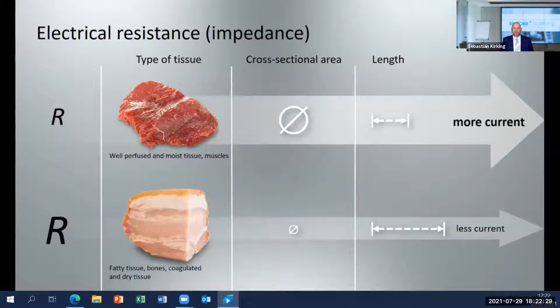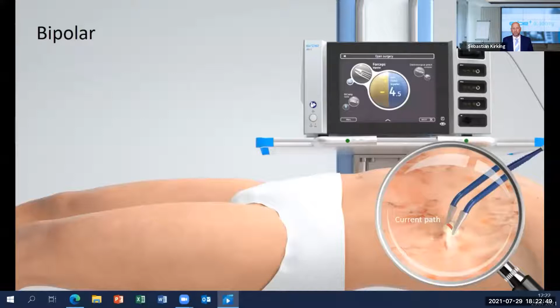Bipolar instruments use the same principle of current density. The difference is that they have an integrated second electrode and do not require a neutral electrode. Still, the patient needs to be part of the electric circuit, just that the electric path now is much shorter.